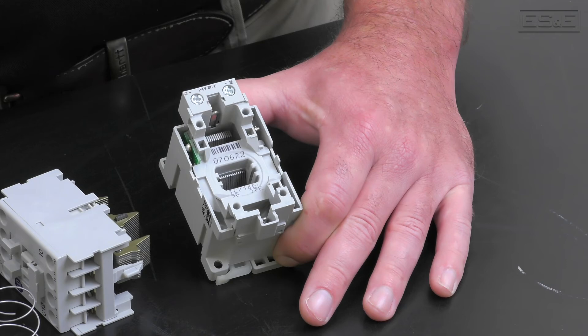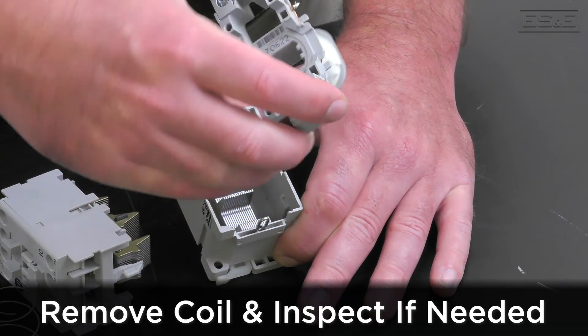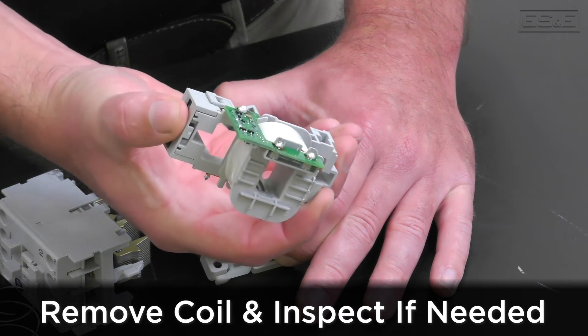Be sure to catch the coil spring and pay attention to its orientation for reassembly. Once you have removed the top cover and the spring, you can lift the coil out of the contactor base and inspect if needed.